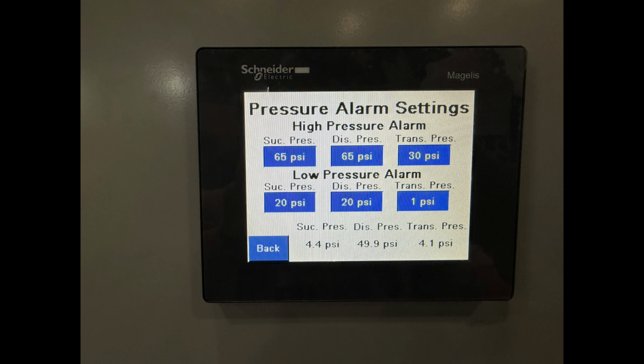Now we can see in the pressure alarm settings that we have high pressure alarm and low pressure alarms. So we have the suction pressure at 65 for the high and suction pressure at 20 psi for the low. Discharge pressure is the same, and at the transmission pressure, 30 psi is the high, 1 psi is the low, because usually that manual valve isn't closed all the way or open all the way, just because we can't keep a very high pressure that we want, and also that affects the flow rate as well.